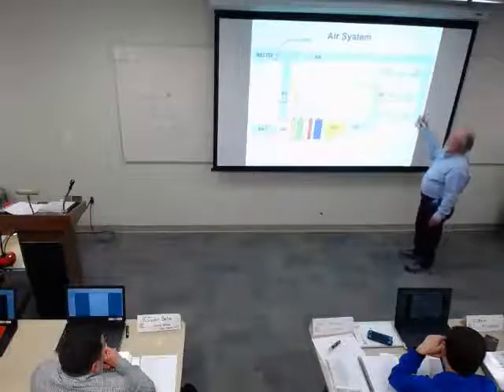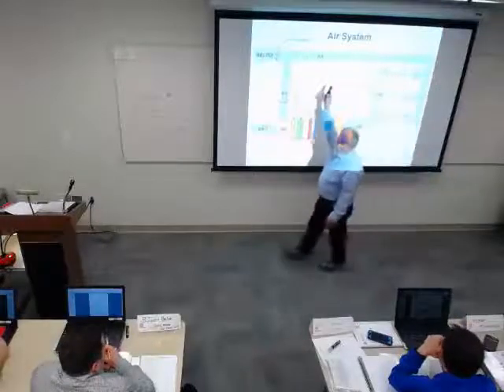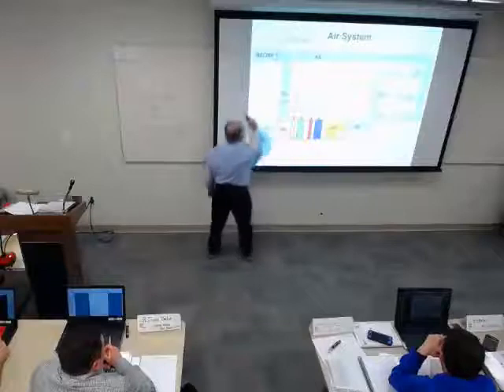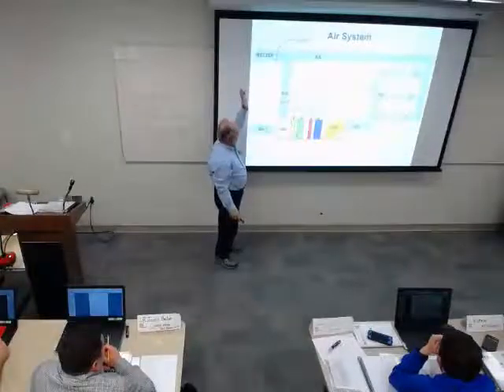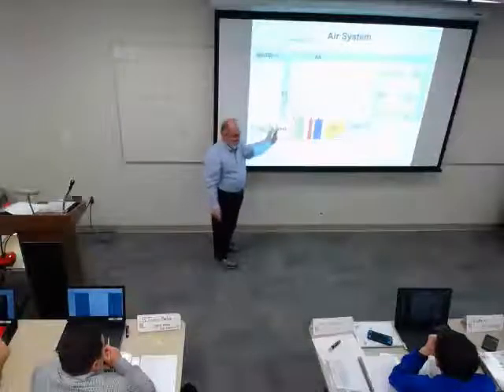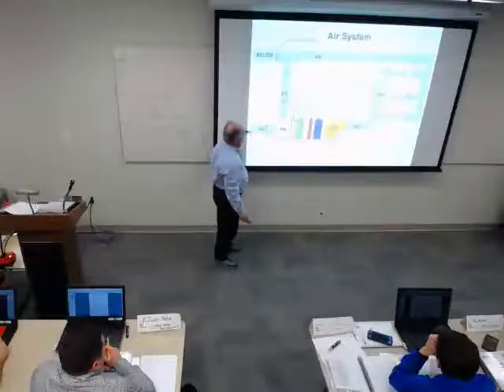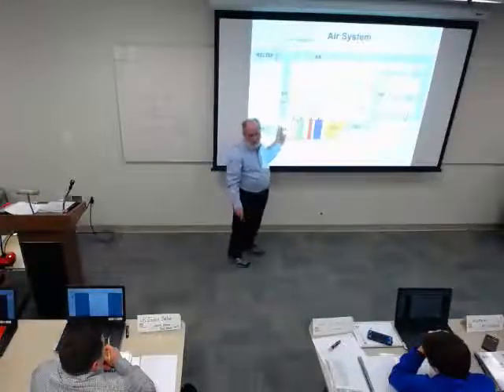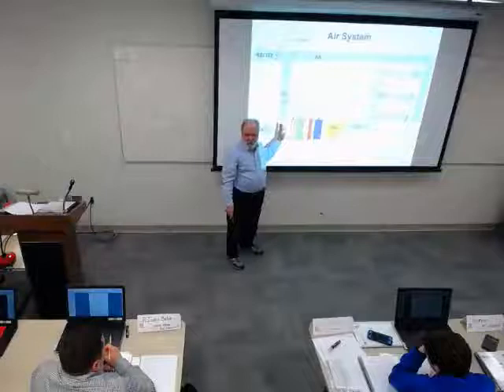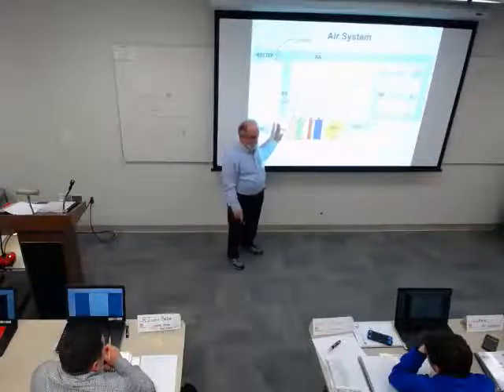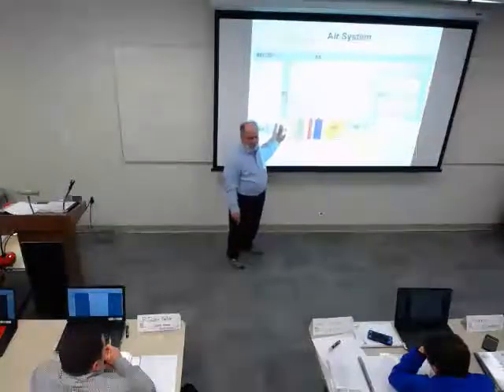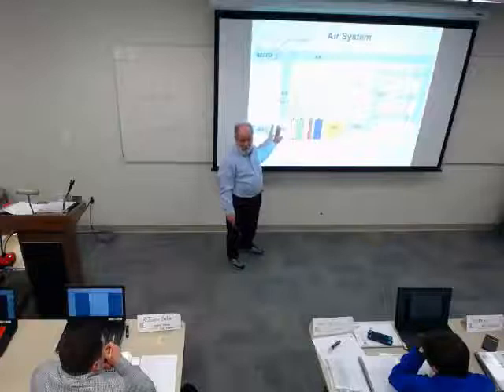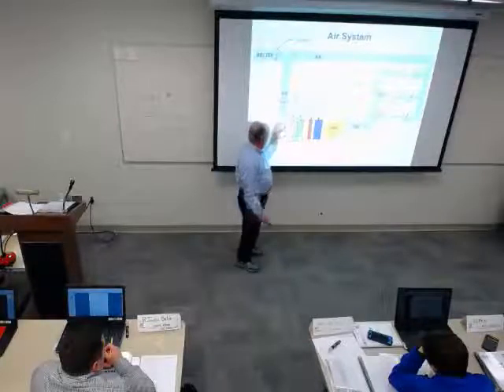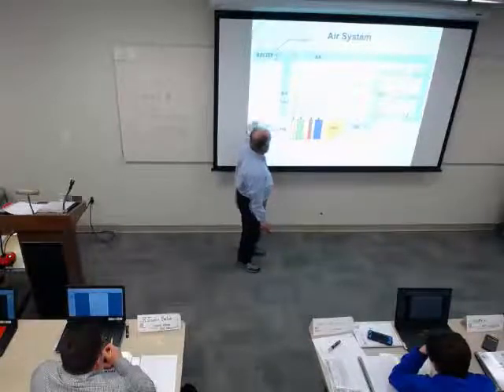In the rooms, the return air comes way back here, and some of that air gets relieved, and some of it comes back in as what we call the return air. And we're bringing in air from the outside. We're bringing it into this. This is called the mixing box. I'm pretty sure all you guys that have QA experience out in the field know the mixing really doesn't happen here. I mean, it can happen here, but you can't count on it. But that's what we call this. Sometimes we have to do something special in that box to make it work.